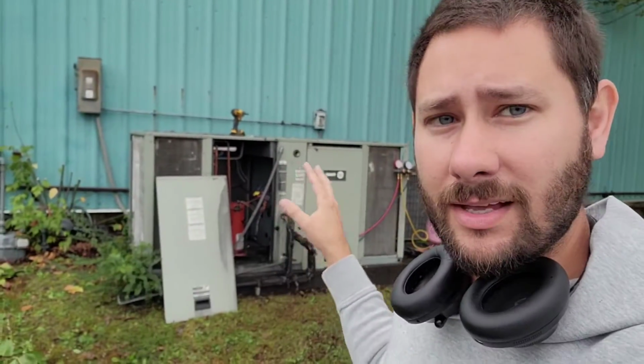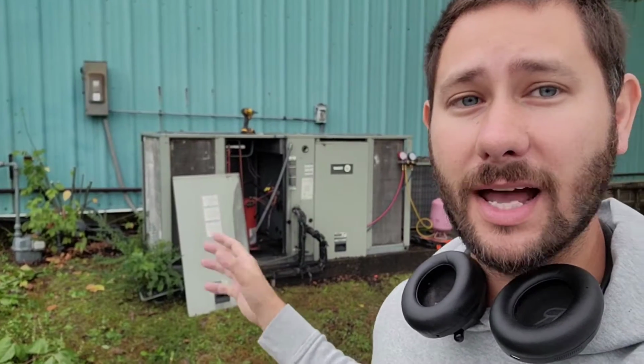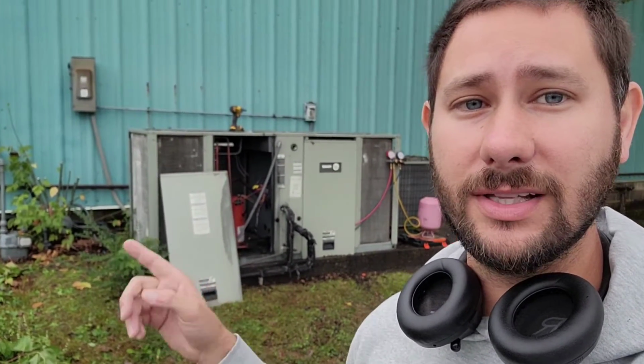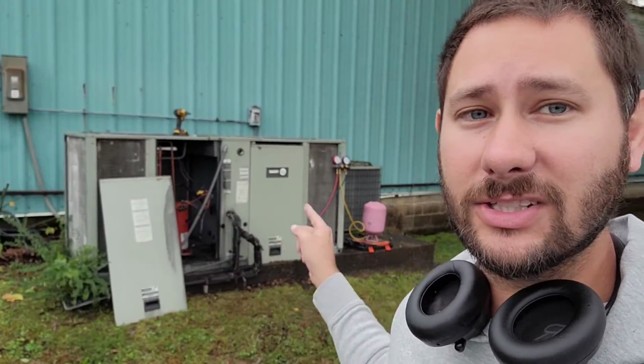Okay, so it had a bad compressor that was shorted to ground, which created that black sooty oil. What I did was close the valves for the section you see the panel off of, and then started this other section.